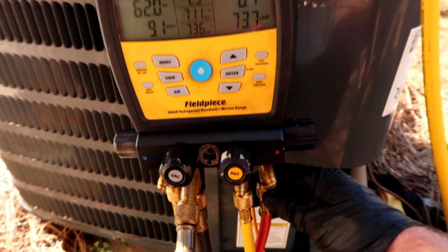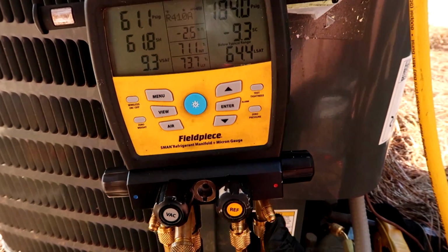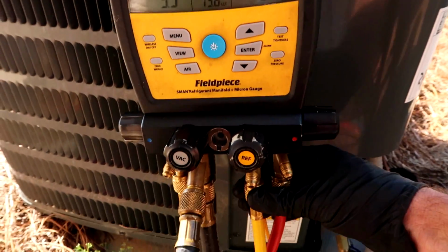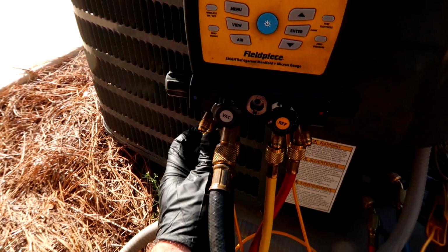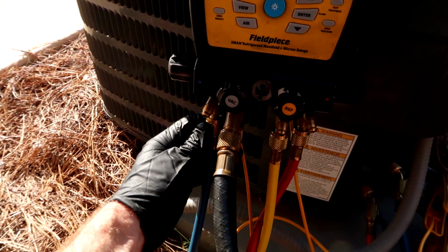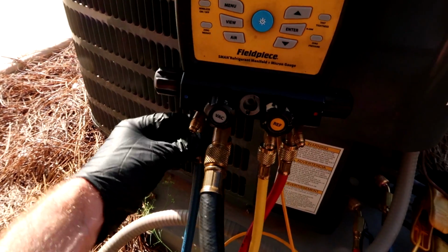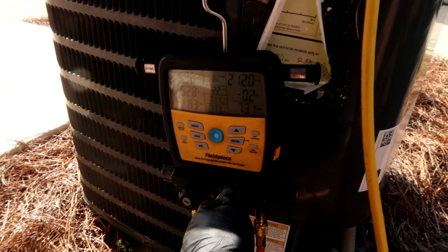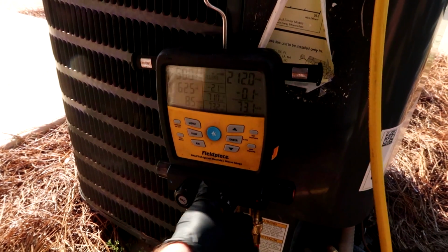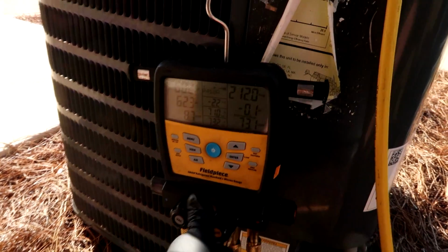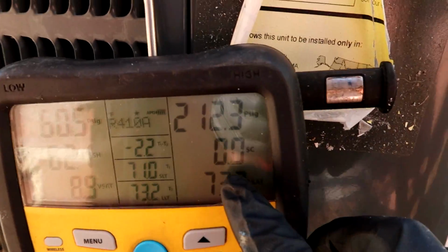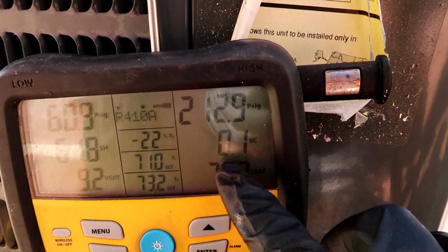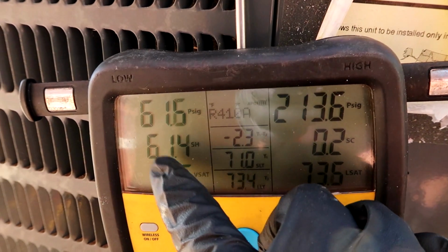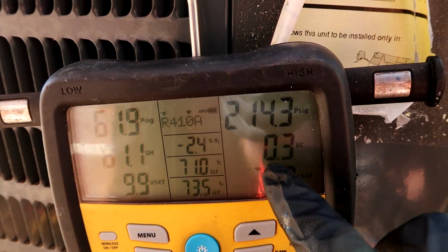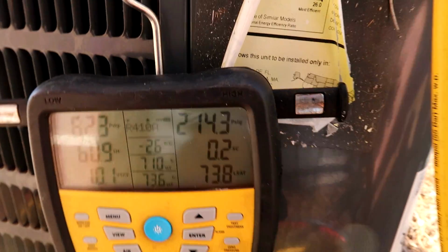So let's get the air out of the system. We don't want air getting in our system here, so I mean get the air out of the lines, that is, not your system. We don't want air getting into the system, and that's why I bleed the line real quick. And now we can enter refrigerant into the mix. So I'm going to get this subcool up to 12 because it's a TXV. If it was a piston up there, I would be worried about the superheat, but since it's a TXV, we're going to get that to 12.